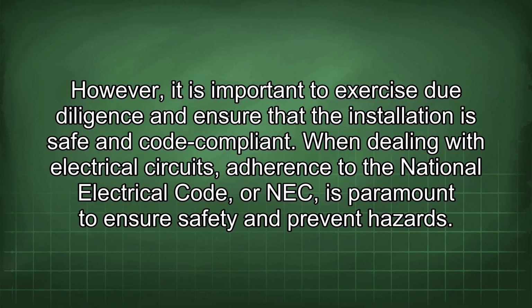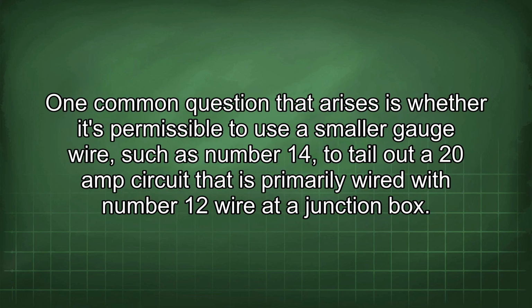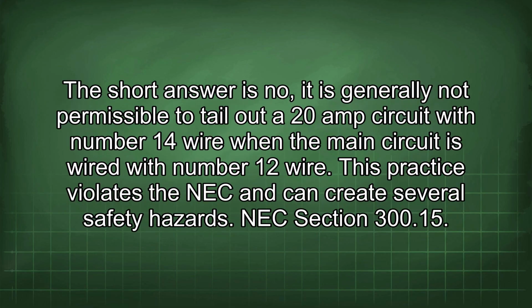When dealing with electrical circuits, adherence to the National Electrical Code, or NEC, is paramount to ensure safety and prevent hazards. One common question that arises is whether it's permissible to use a smaller gauge wire, such as number 14, to tail out a 20 amp circuit that is primarily wired with number 12 wire at a junction box. The short answer is no.